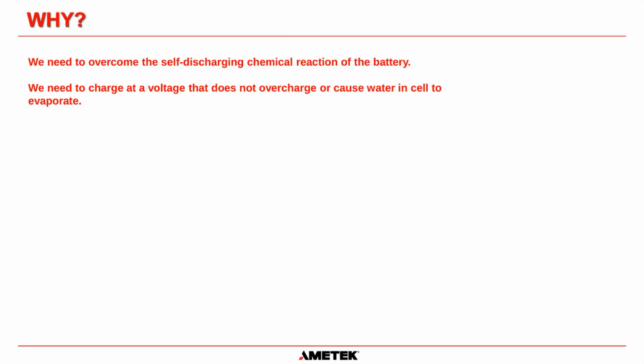If you just left a battery fully charged in a warehouse at 77 degrees Fahrenheit, over a period of 6 months, that battery will start to internally self-discharge. And after 6 months, you would have to perform a charge on that battery. It's just inherently what happens because of the chemical reaction within the battery itself. So the battery manufacturer has done a lot of research, and they've worked out a charge voltage that does not overcharge or cause water in the cell to evaporate excessively, and it also overcomes the self-discharging chemical reaction of the battery. So that's what float charge means. You can leave it on float charge for pretty much forever, and you will only have to do minimal water replacement in that cell. That's the theory anyway.